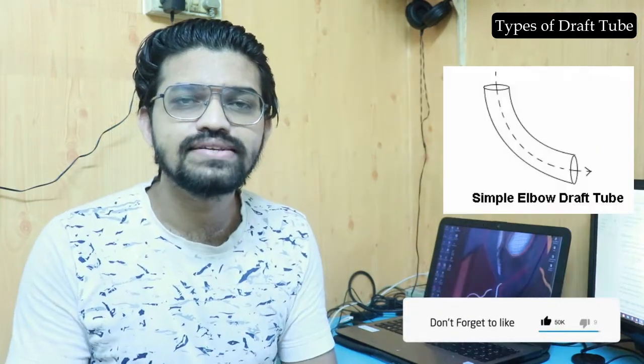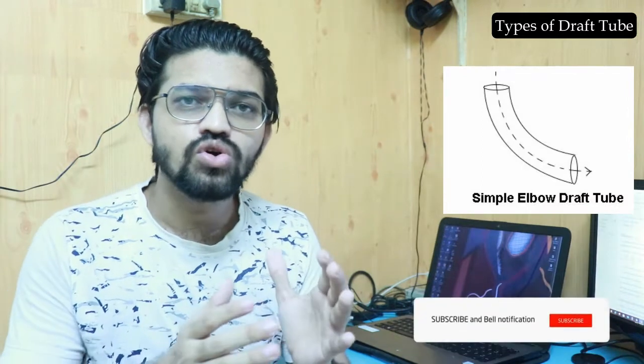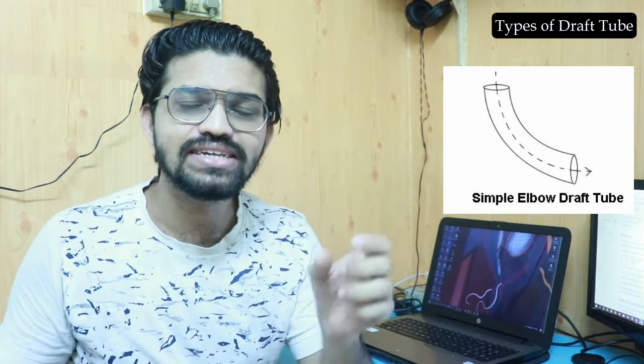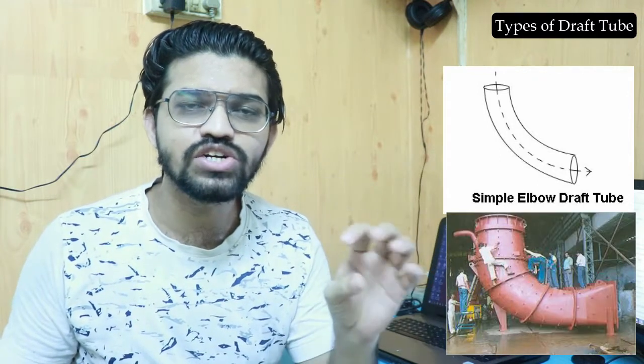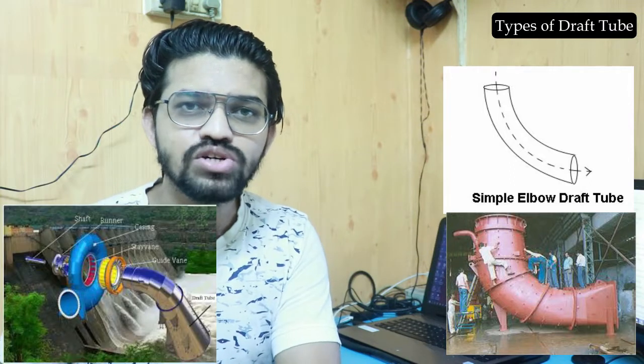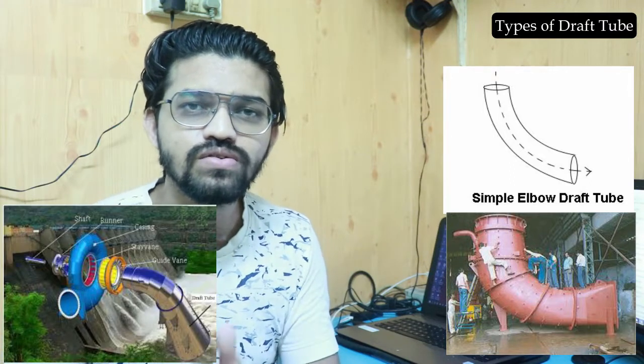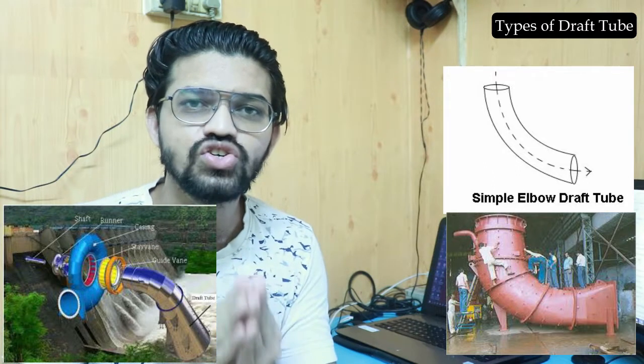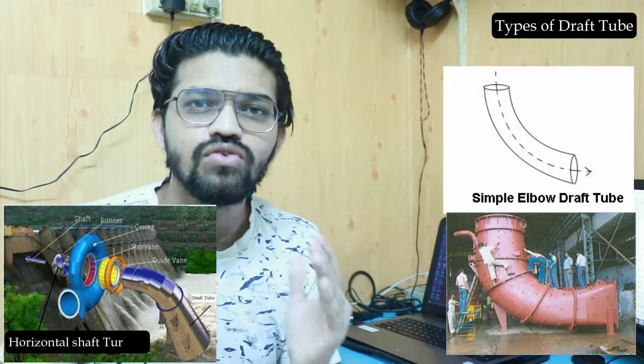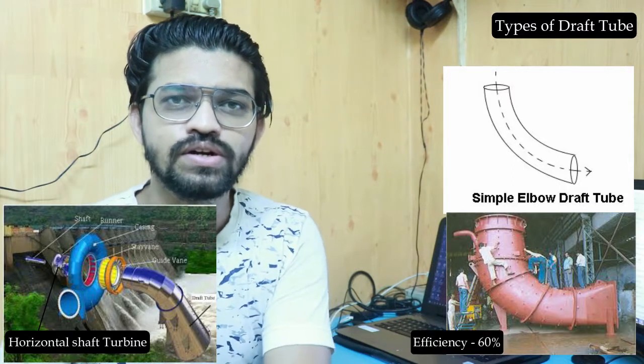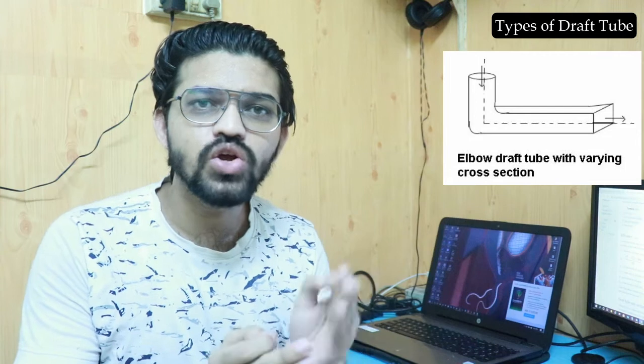The next type is the simple elbow draft tube. This type of draft tube is bent at 90 degrees — one end is connected to the exit of the turbine and the second end is immersed into the water. This type is suitable for the horizontal shaft, horizontal axis Francis turbine, and it provides efficiencies up to 60%.